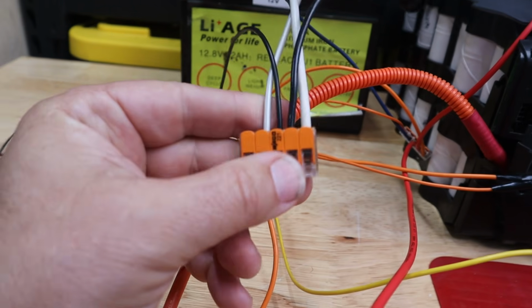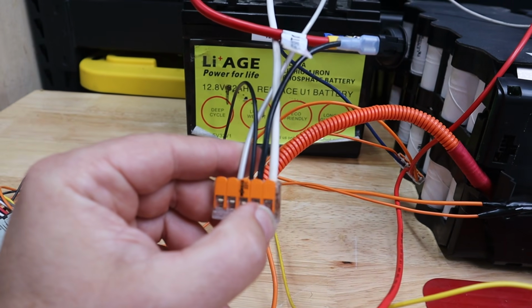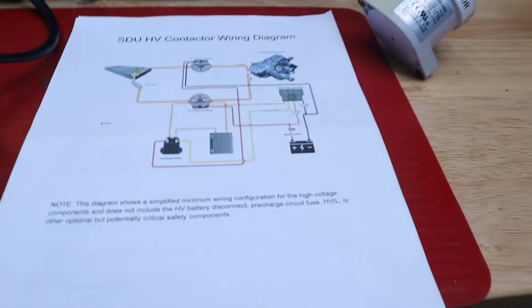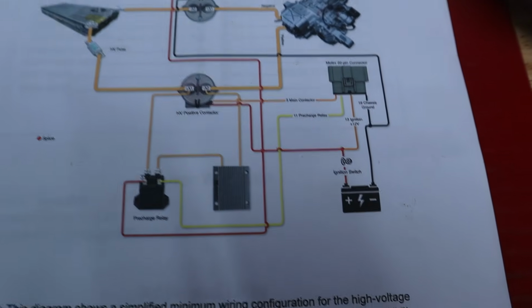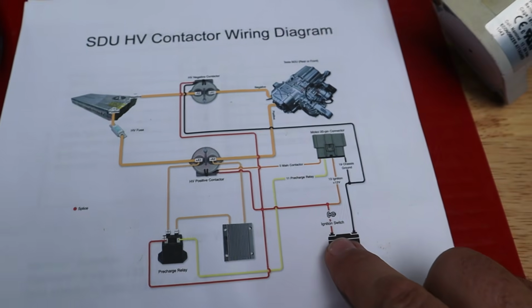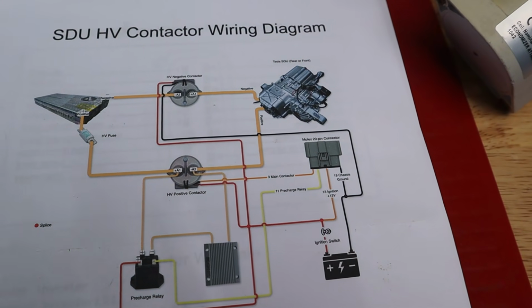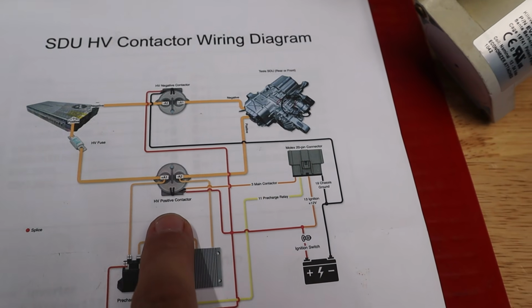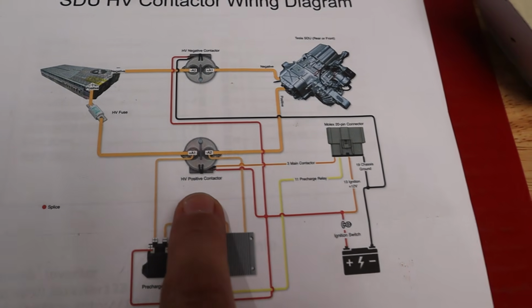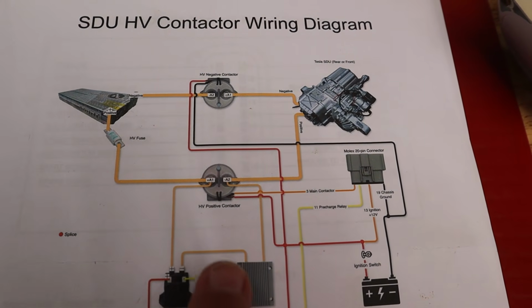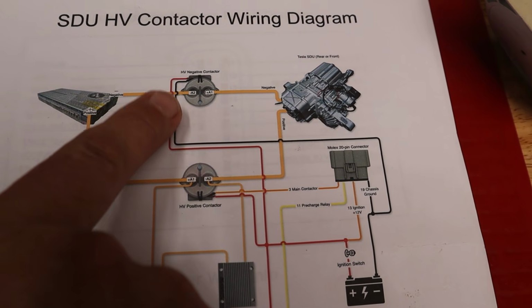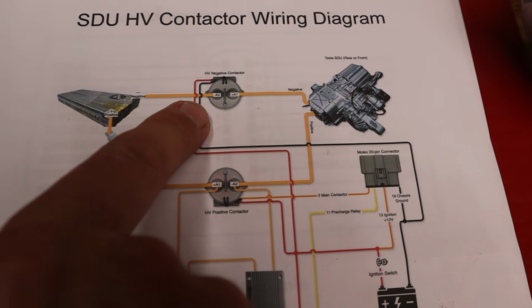So in this case, it's kind of acting like a little positive bus bar. And if we look on our diagram down here, that switched power is going to the pre-charge relay. It's going to the coil on the positive contactor. It's going to power on the coil on the negative contactor.